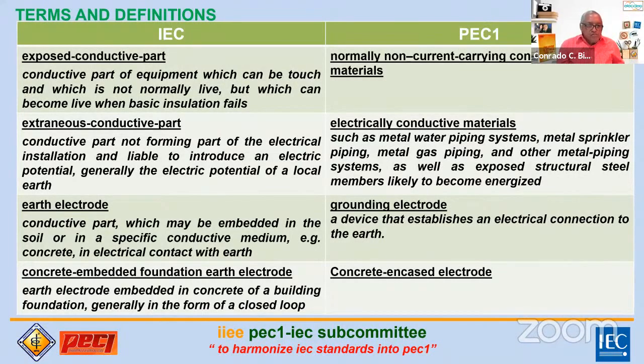Meron din tayong tinatawag na extraneous conductive part. Okay, what are these? These are the conductive parts not forming a part of the electrical installation, but they are liable to introduce an electric potential, generally the electric potential of a local earth. Dito sa PEC, ganito naman yan, pareho lang. So electrically conductive materials such as metal water piping system, metal sprinkler piping system, metal gas piping, and other metal pipings, as well as exposed structural steel members which are likely to become energized. So pag nasa industrial plant ka, napakaraming doon mga metal, di ba? Pag nasa parking area ka na made up of steel structure, so all these things ay tinatawag natin na extraneous conductive part, which needs to be bonded or connected to earth.